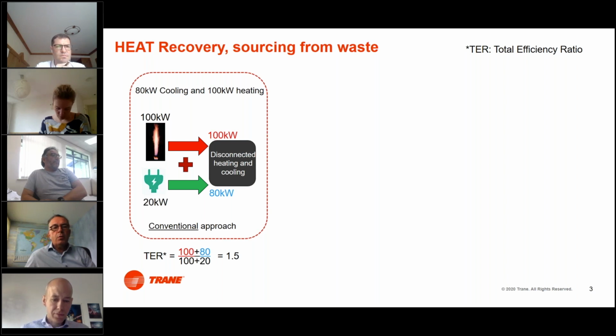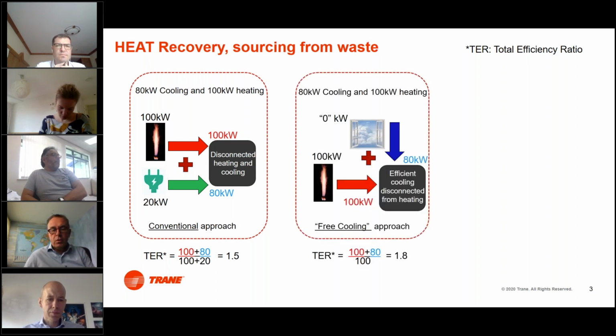Now, this has been a very common approach for many years, and for process applications and also data centers, by the way, that have a wintertime cooling need, we started to improve those efficiencies by creating free cooling. It's a commonly known theme. Free cooling is about opening the windows when it's cold outside. So you're still combusting fossil fuel to create heating on one side of the process or the building, and on the other end, you're opening the window so that you have free cooling where you want cooling at winter conditions or lower climate conditions. And it is improving the efficiency.